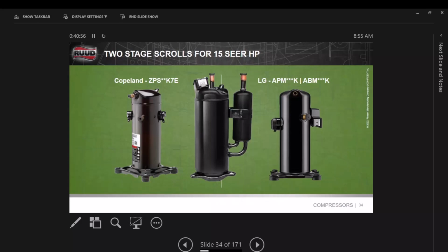It's got just a 24-volt coil on it, where that's a DC coil inside that compressor. So we're taking 24 volts from our board going to this compressor. Right at the plug of that compressor is a rectifier. It changes it to DC. So if you've ever had a short in the system and you couldn't find it, I bet you anything it's in that rectifier. We got a video.